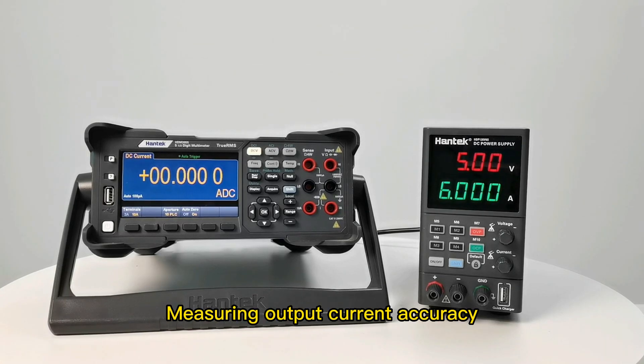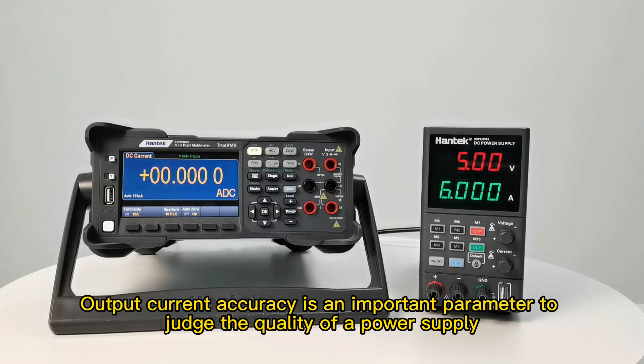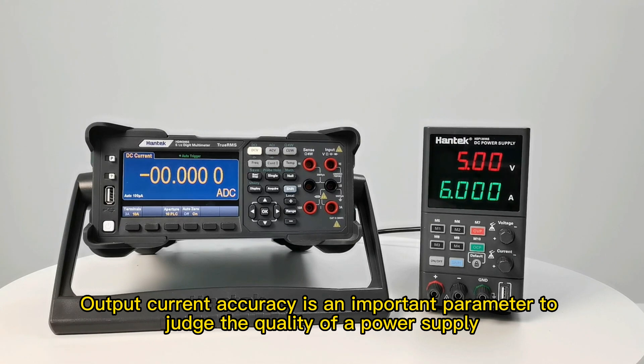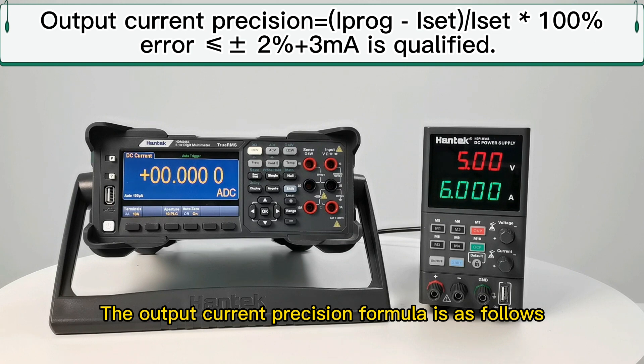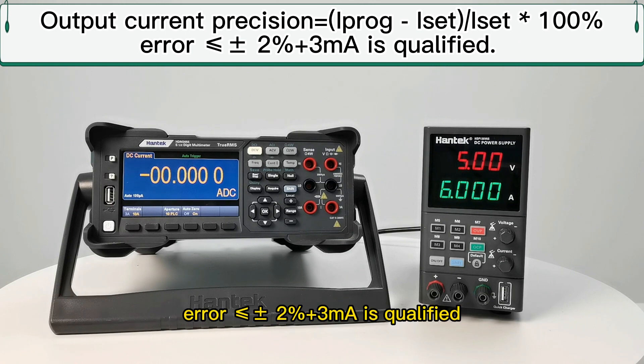Output current accuracy is an important parameter to judge the quality of a power supply. The output current precision formula is as follows: (Iprog - Iset)/Iset × 100%. Error ≤ ±2% + 3mA is qualified.